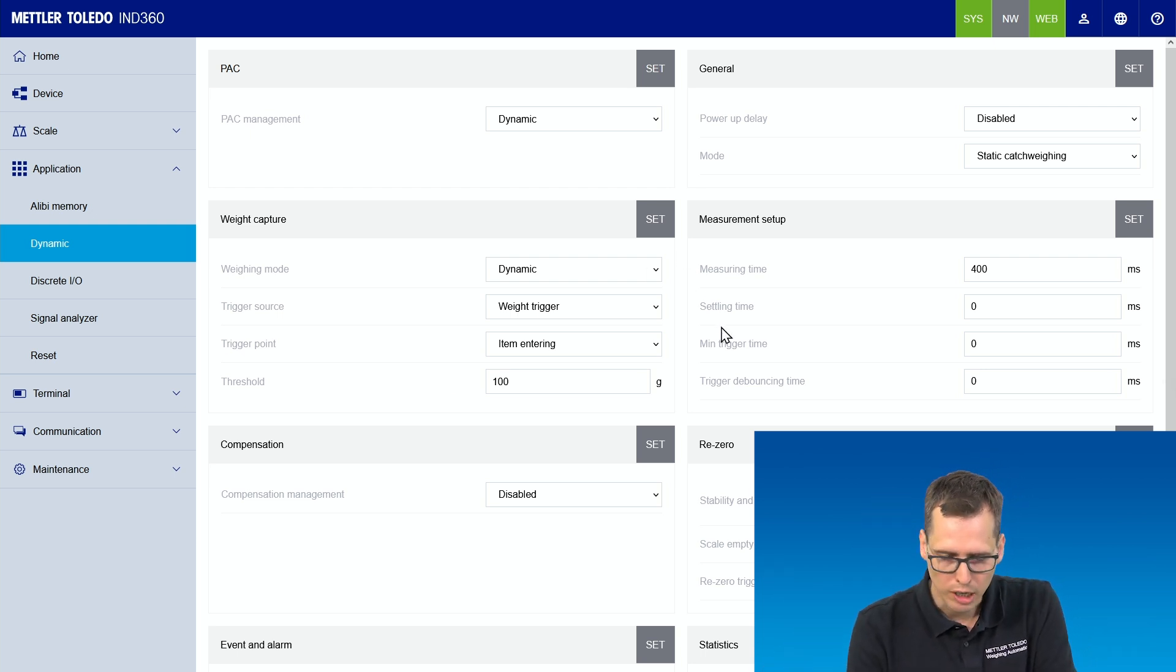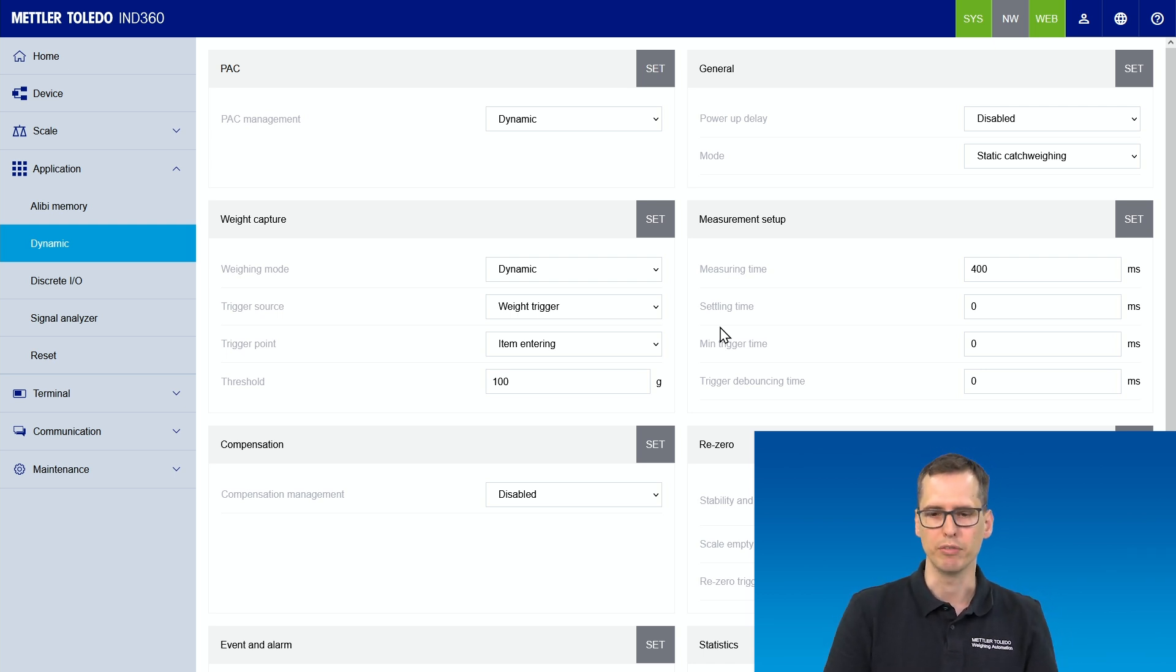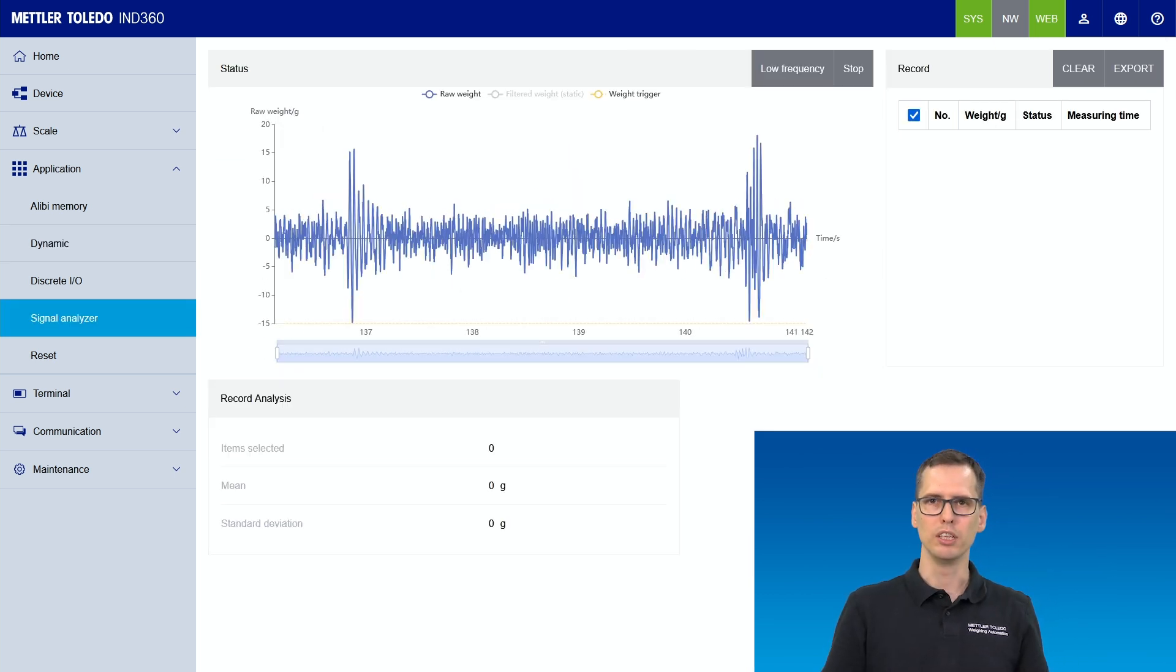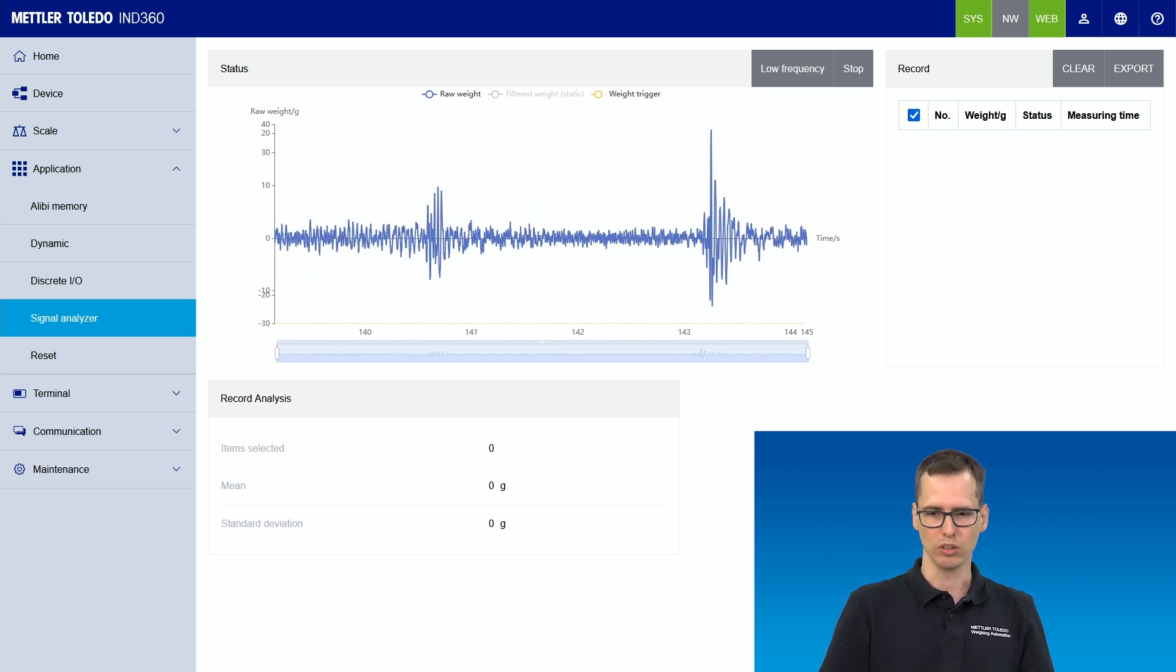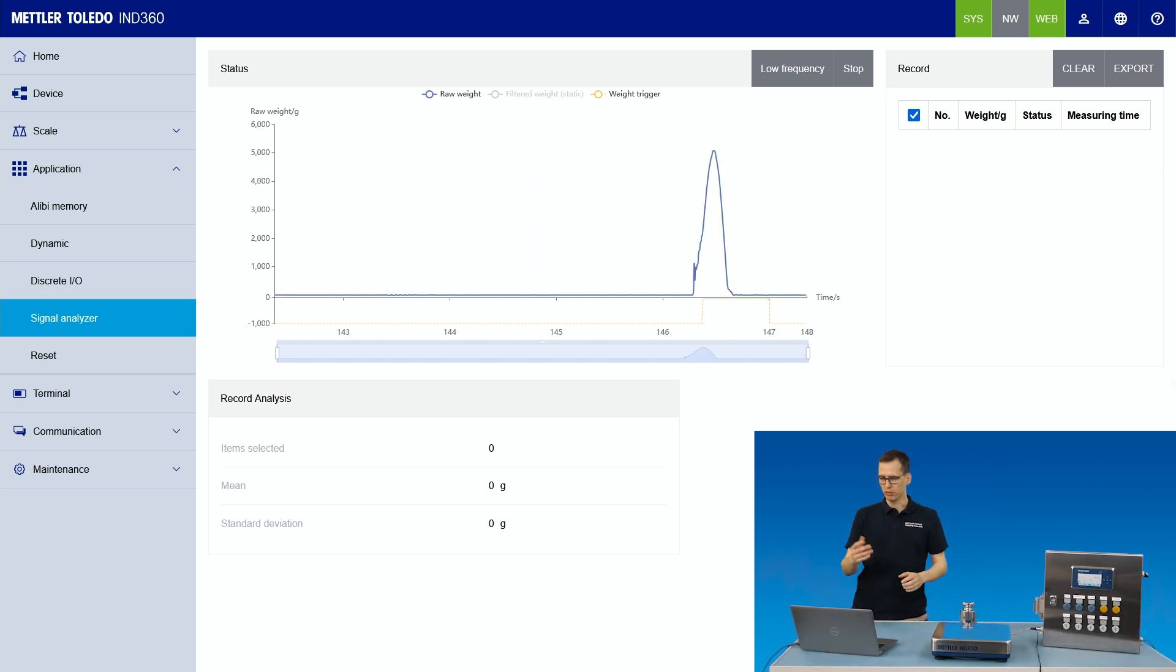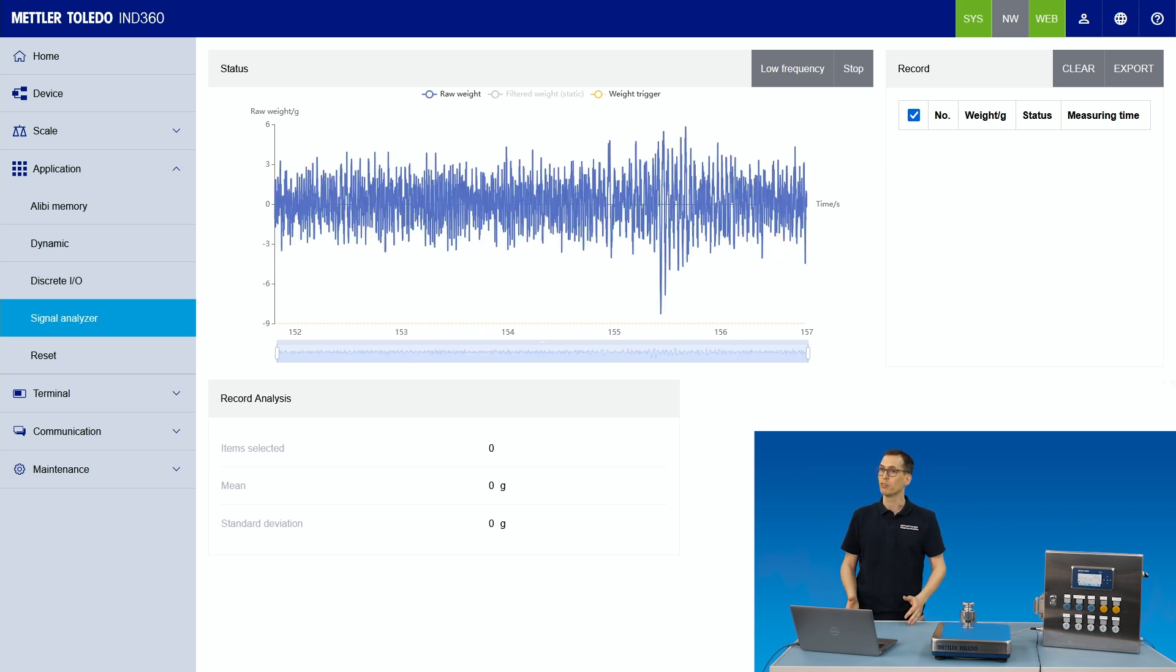The measuring time and settling time, that's something we need now to figure out for this particular setup I have here. For that, we go to the signal analyzer tab where we see a live representation of the weight signal on the scale. So touching the scale, we see that immediately as a peak here in the signal analyzer. So I will now start the application and we will capture our first couple of weighing traces.